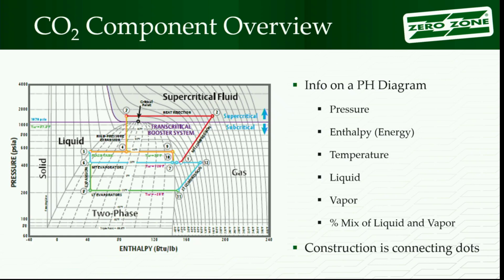So the pressure is going up on the left-hand side. Across the bottom then is the enthalpy. Enthalpy is kind of a fancy term for energy. So I start on the left-hand side when it represents what's happening in the system. As I move from the left to the right, I'm gaining energy. So when an evaporator is drawn on here, I start out at the evaporator on the left-hand side. Got a lot of liquid in there. It's absorbing energy, right? It's cooling the air. The refrigerant's warming up or gaining energy. As it gains energy, it's shown going across to the right-hand side. So it has energy on it.